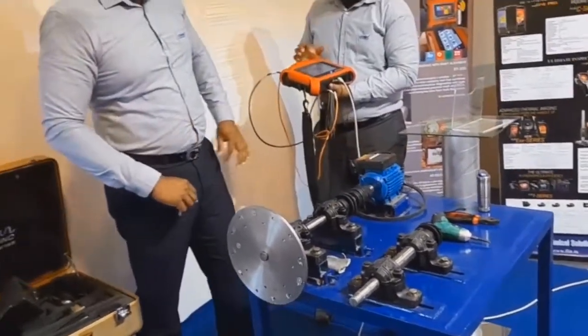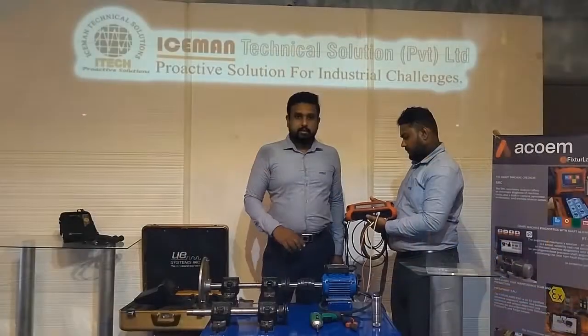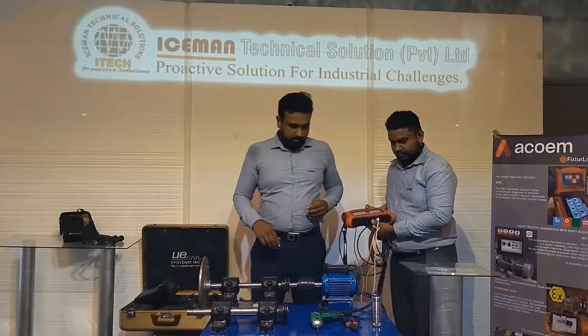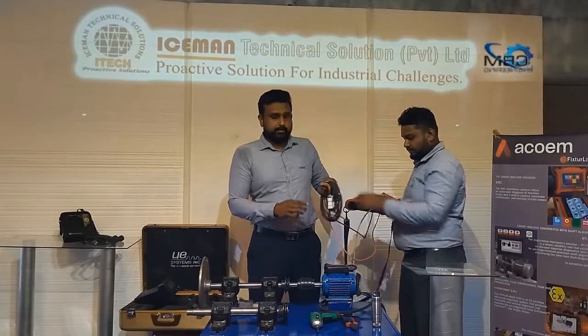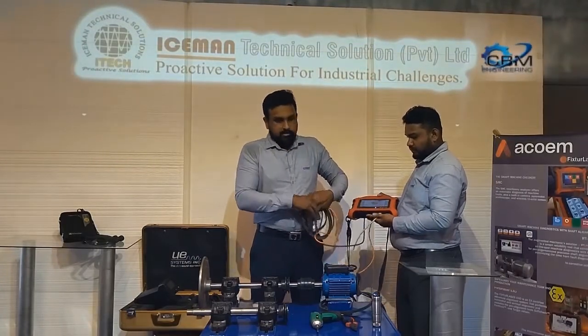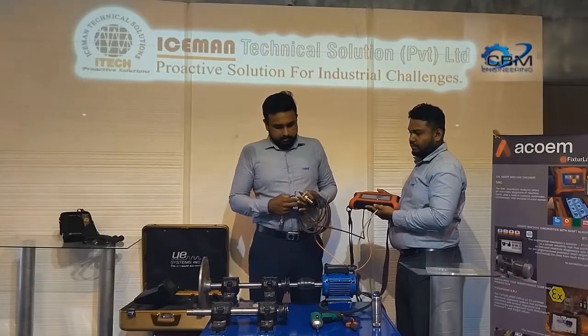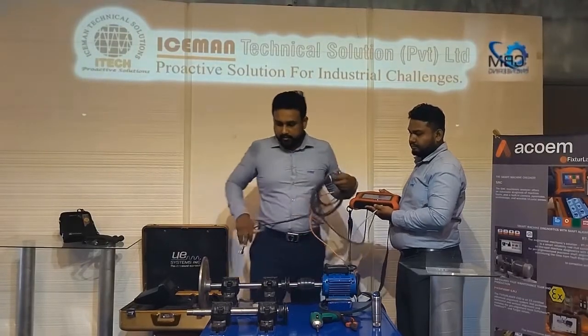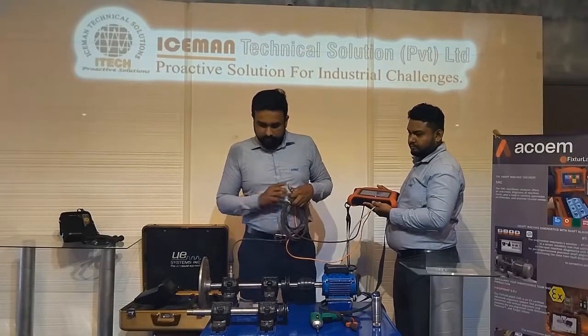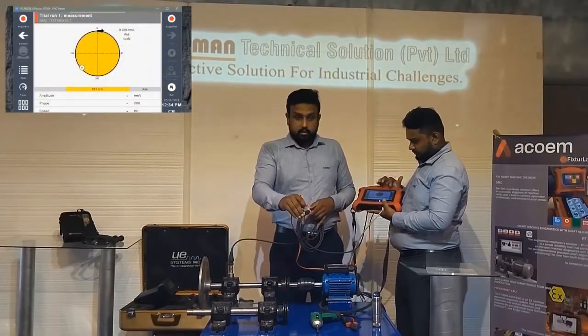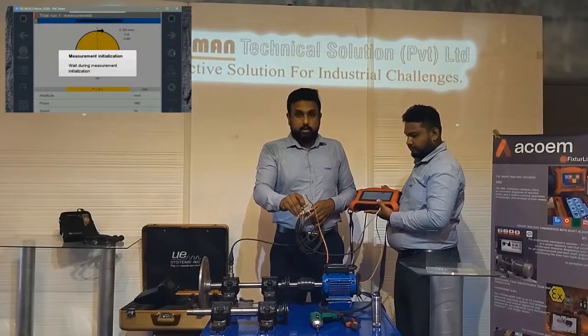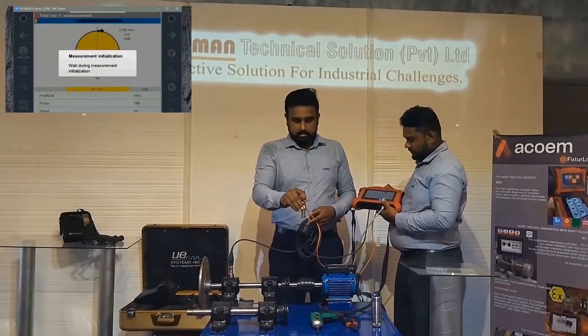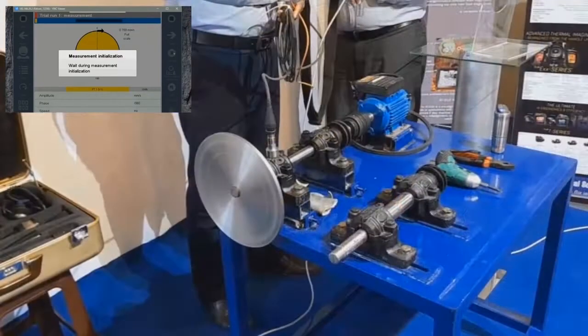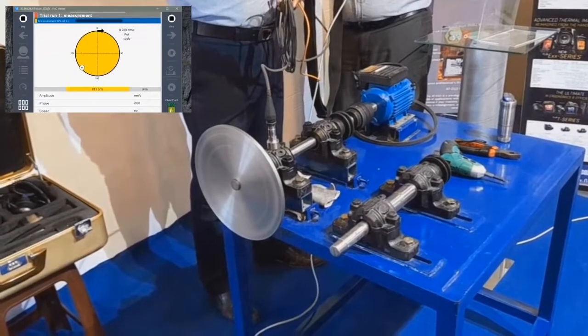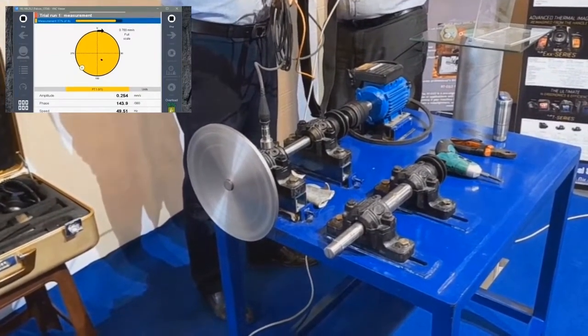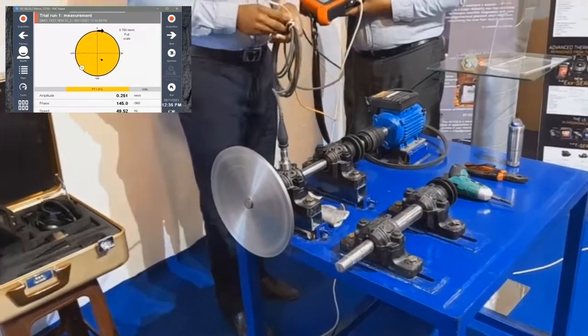After adding the trial weight, how does the trial vibration vary? Always we want to take the vibration at full RPM, in full running condition, same as the previous one. We put the sensor here and place the tachometer here. This measurement is called the trial weight measurement. Okay, we take the trial weight measurement.